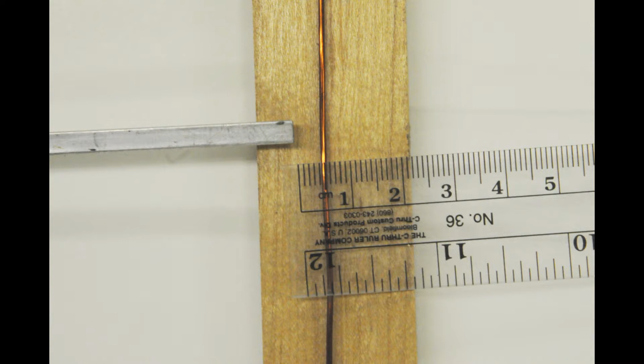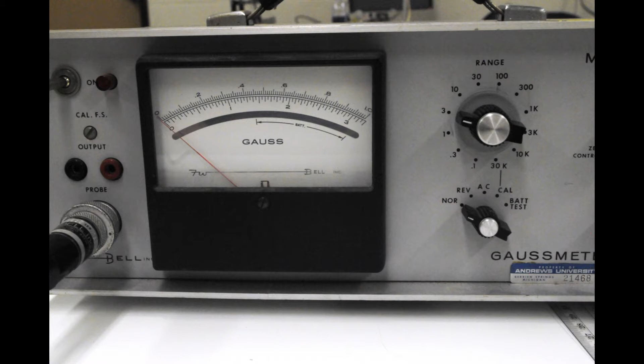When the range dial on the right is set for a maximum value of 0.3, 3, or 30 Gauss, then the bottom scale is used. But when the range dial is set for 0.1, 1, or 10 Gauss maximum, then the upper scale is used.